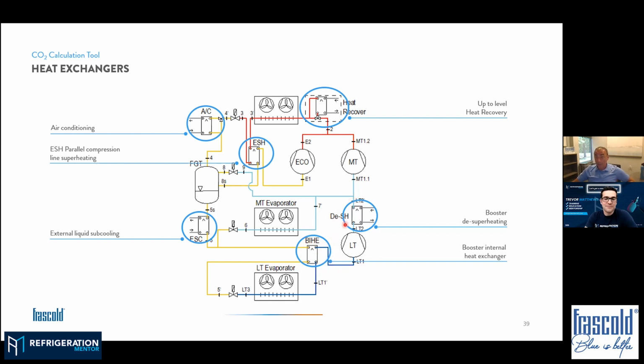It's also a life changer for the medium temp compressor, because if we have too high suction gas superheat, we can lower the superheat with the de-superheater, which can act like heat recovery. We've seen this a lot for floor heating, for example, on low temperature applications. So it's heat that can be recovered.